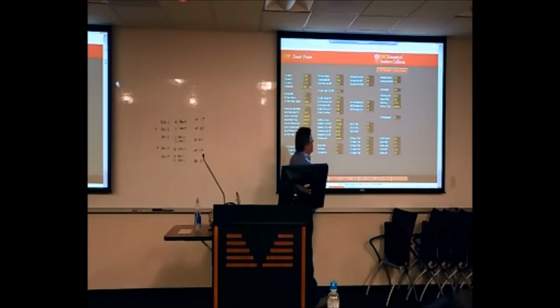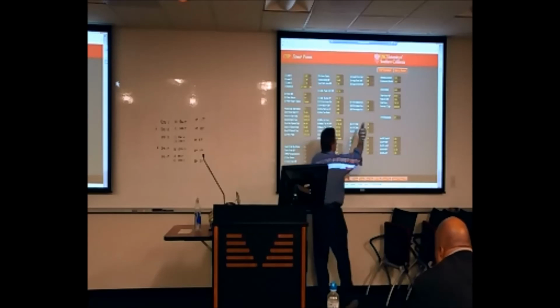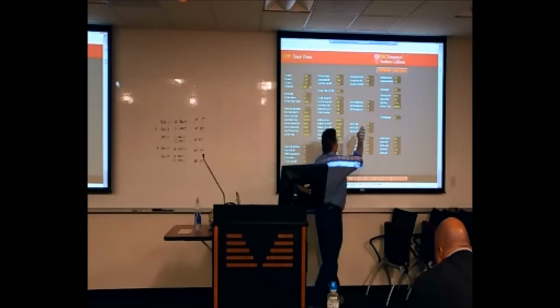Chill water, condenser water delta T at the worst case operating chiller. And then up in the upper right, we see the cooling tower auto lead lag switch and the condenser water pump auto lead lag switch. So right now we're in 1. That's just mode 1. It'll go to mode 2 and then to mode 3, then back to mode 1. If there were a desire to automatically change who you wanted in the lead, those can just be manually set to 2 or 3 to throw the right tower in the lead. For instance, 3 would have tower 3 be in the lead, or pump number 3 be in the lead. So you could rotate the lead manually if you wanted to. Right now it does an auto rotation once a week.